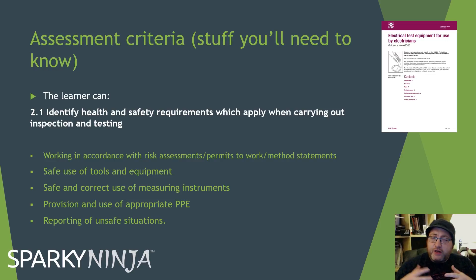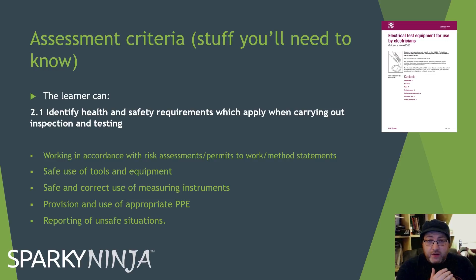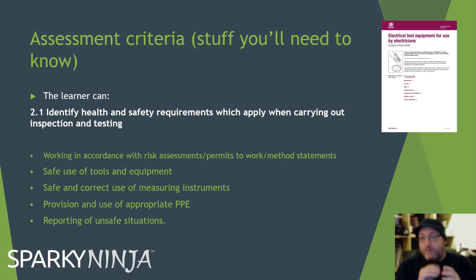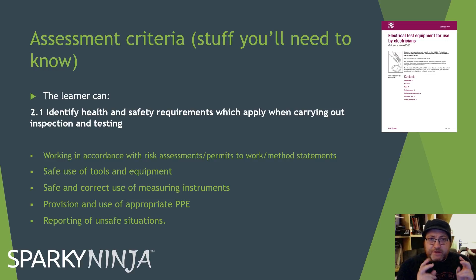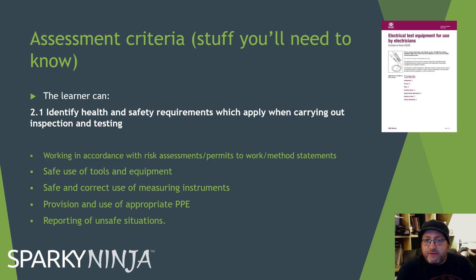If your method of work doesn't match the customer's method of work, you've got an issue to solve. You carry out a risk assessment, develop a system of work, and look at the site — which might be domestic, industrial, or agricultural. Make sure they work together. All this should be done at the pre-survey point. You'll determine what tools and equipment to use. Standard multifunction testers (MFTs) should be in a good condition, state of good repair with charged batteries.